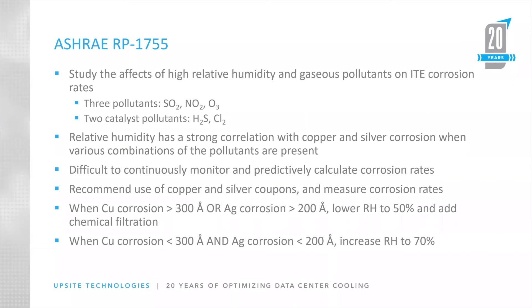As a reminder, the recommended range upper relative humidity is 60% from the fourth edition. So here we're actually saying we are lowering that relative humidity relative to the fourth edition if you have these pollutants and this corrosion activity going on. However, if you put those coupons in place and see corrosion rates less than 300 angstroms for copper and 200 angstroms for silver, you can feel comfortable increasing your relative humidity up to 70%. This is part of the recommended range adjustment, not an allowable range adjustment.